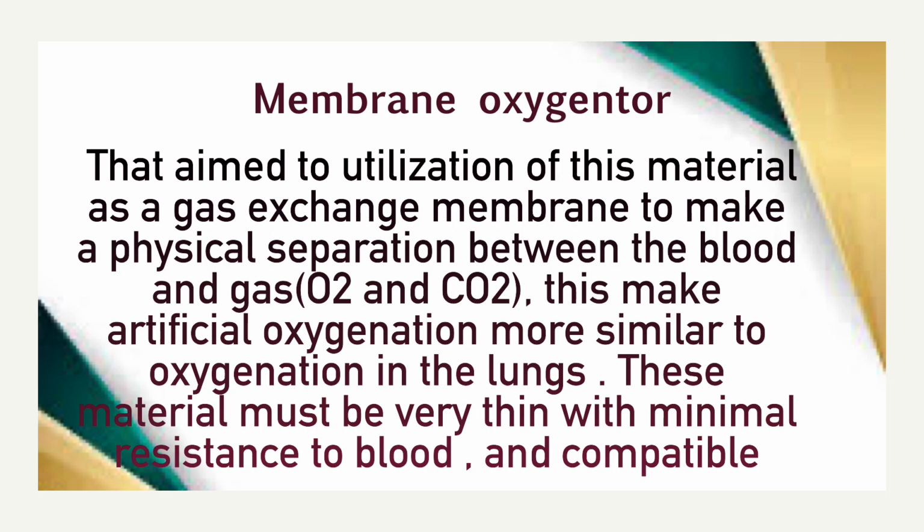The membrane oxygenator aims to use a material as a gas exchange membrane to make a physical separation between the blood and the gases, O2 and CO2. This makes artificial oxygenation more similar to oxygenation in the lung. This material must be very thin, with minimal resistance to blood, and compatible.